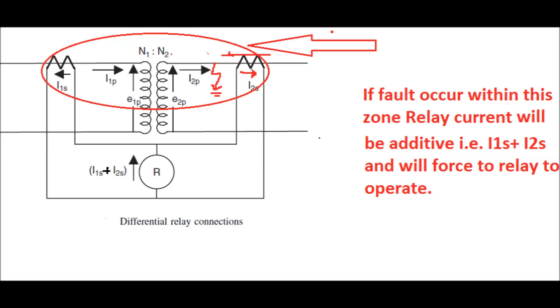But during a fault in this zone, the relay current is no longer I1s minus I2s — it will be I1s plus I2s, as shown in this figure. Hence, the relay will send a trip signal. This is the basic principle of the differential relay.